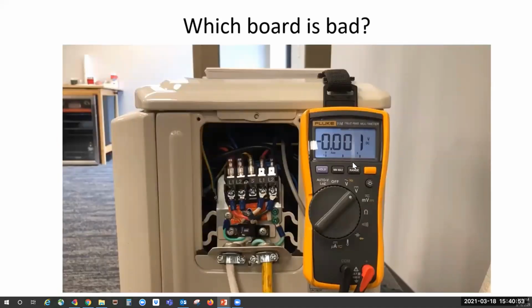Now we need to figure out which board is bad, the indoor or outdoor board. With the S wire connected indoors and the S wire disconnected from the outdoor unit, and the unit powered up, the positioning of your black and red leads is very crucial. You want to position your red lead on L2, and the black lead on the S terminal of the outdoor unit. Now we're looking for negative volts DC with a little bit of pulsating. If you do not see negative volts DC at the S terminal on the outdoor unit, then the outdoor board is bad.